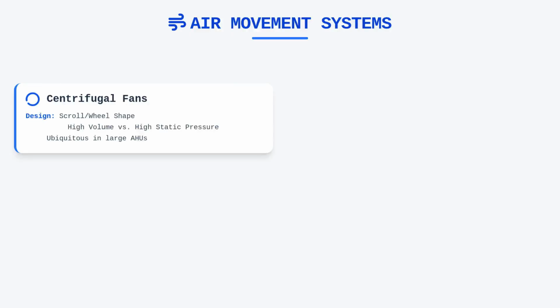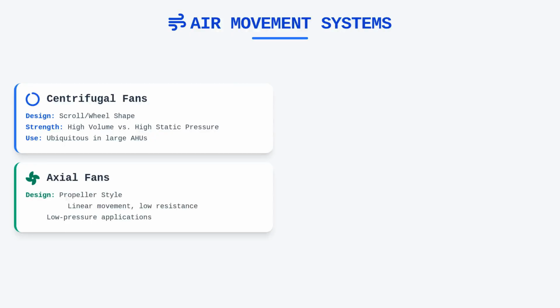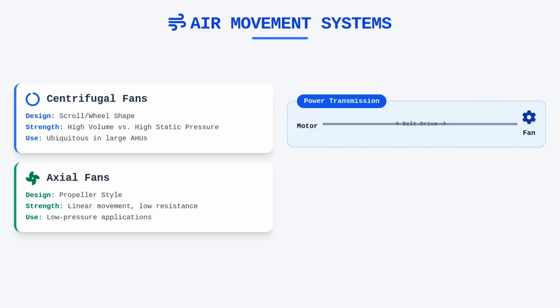Movement of air through the system relies heavily on blowers and motors, which are configured differently depending on the specific application and unit design. Centrifugal fans, often characterized by a scroll or wheel shape, are ubiquitous in large AHUs due to their capability to move high volumes of air against significant static pressure. In contrast, axial fans, which look more like propellers, are usually employed in applications where air needs to be moved linearly with less resistance. The power transmission from the motor to the fan generally occurs via belt drive systems, which require meticulous alignment and tensioning to prevent premature wear.